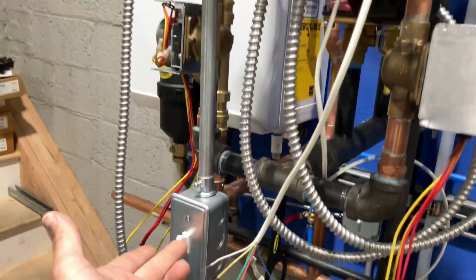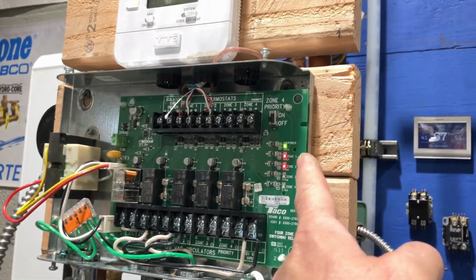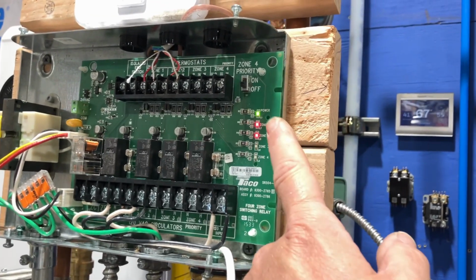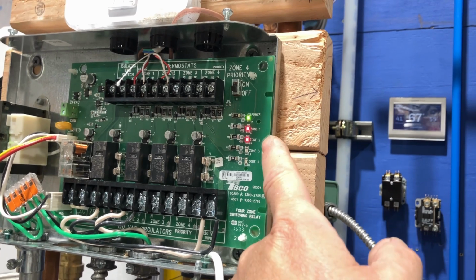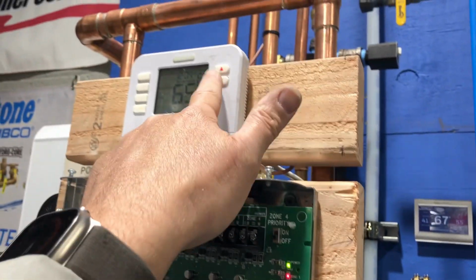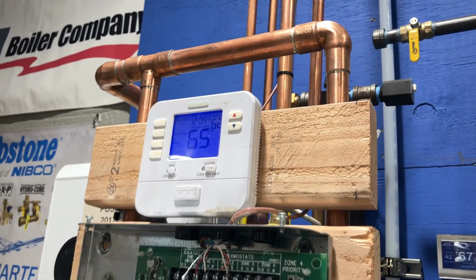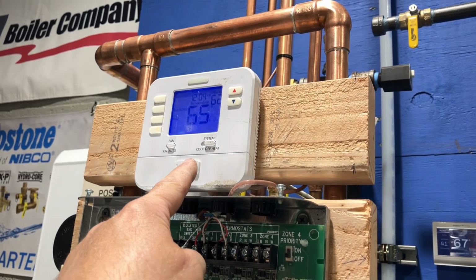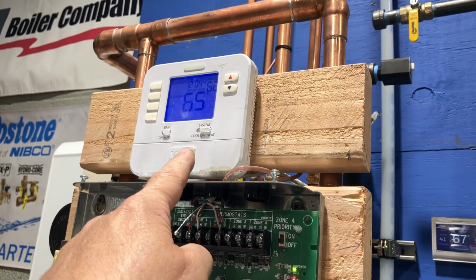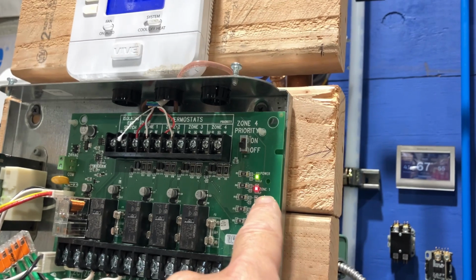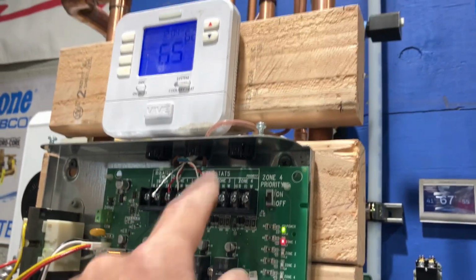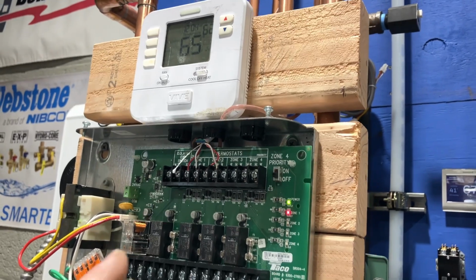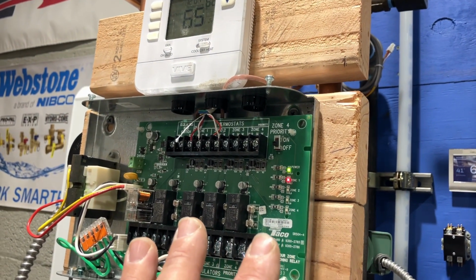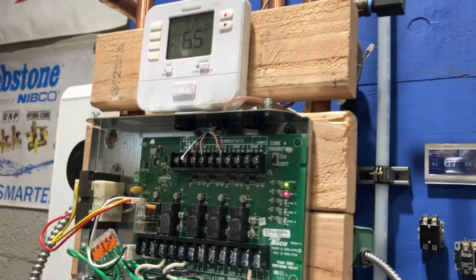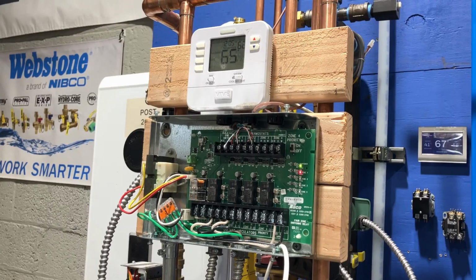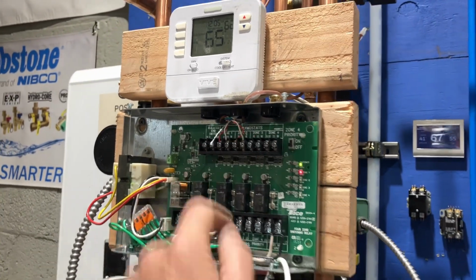Let's turn on power. Right now you see the green light for power is illuminated. We have zone 1, a red light illuminated. Zone 2, a red light is illuminated. Let's see what happens when we lower that thermostat. Wait for that click. I didn't even hear the click. Did you hear the click? Yeah, I did. Okay. Zone 2 is off. The only zone on right now is zone 1, which is going to another system. So for training purposes, let's disconnect the white wire from zone 1. From zone 1? Yep. Okay.